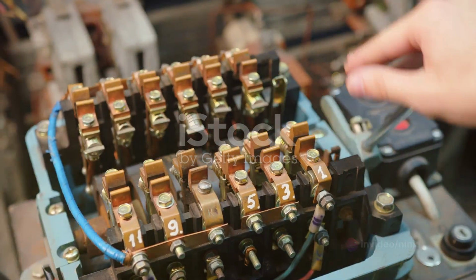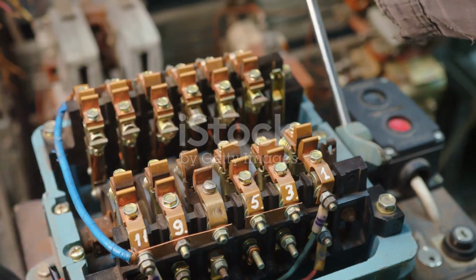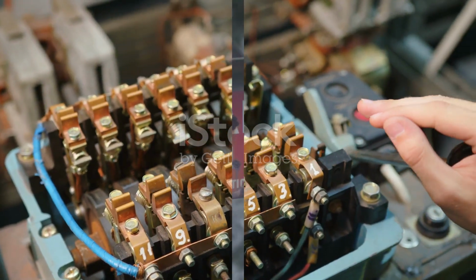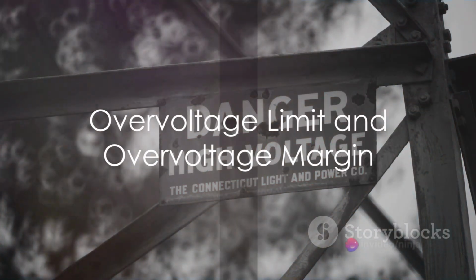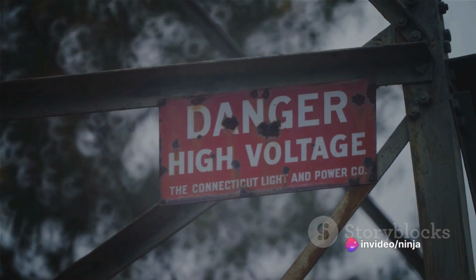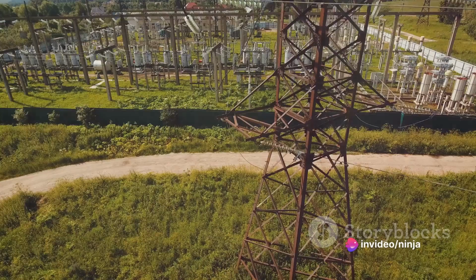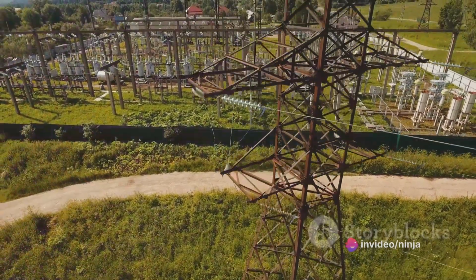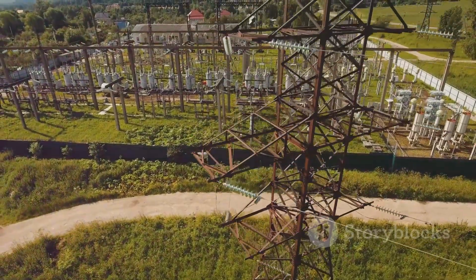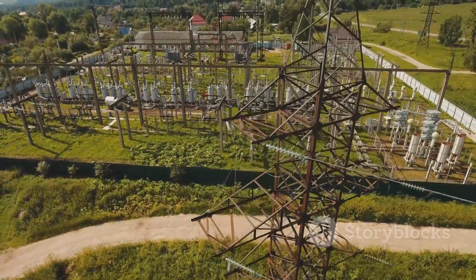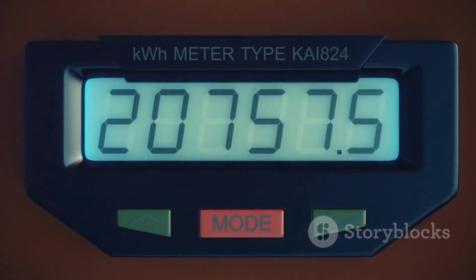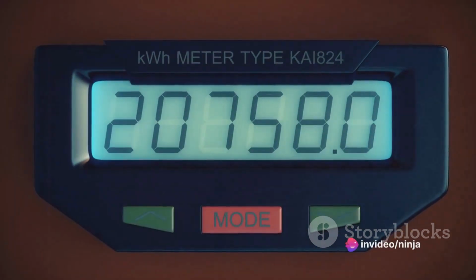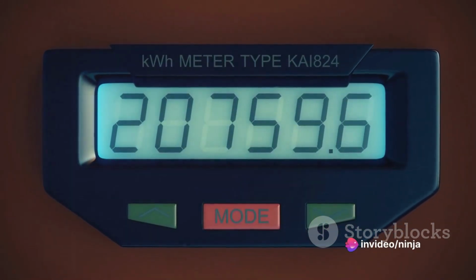The voltage for the most remote customer during maximum load should still be above the undervoltage limit. However, during low load, the voltage should not exceed the overvoltage limit for any of the customers. The critical case for overvoltages is not the most remote customer, but the one nearest to the main substation with voltage boosting. The difference between the highest voltage magnitude for a given customer and the overvoltage limit is referred to as the overvoltage margin.